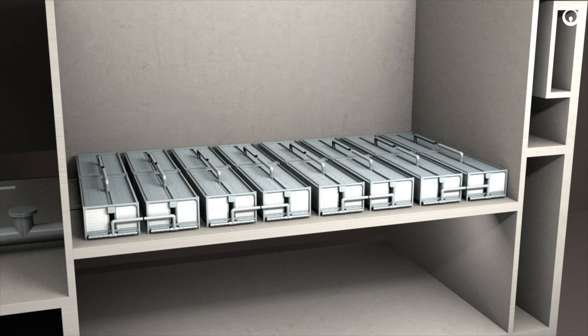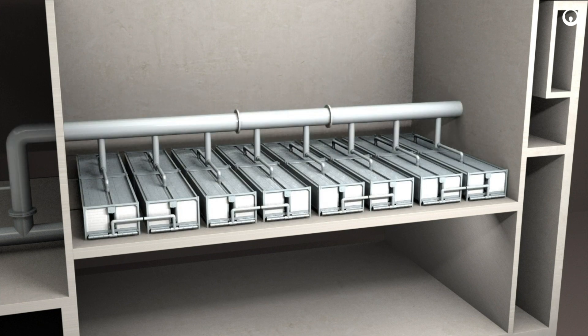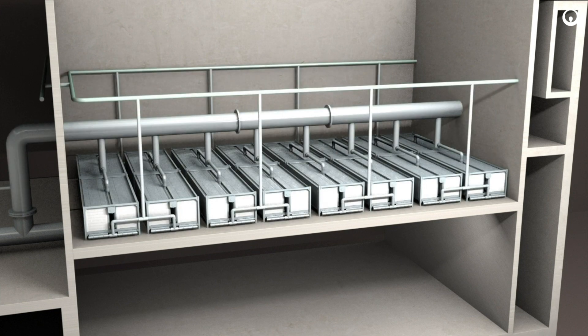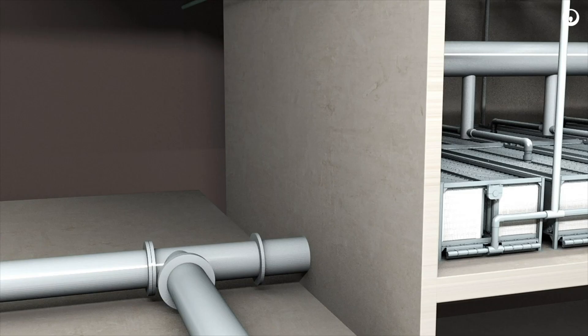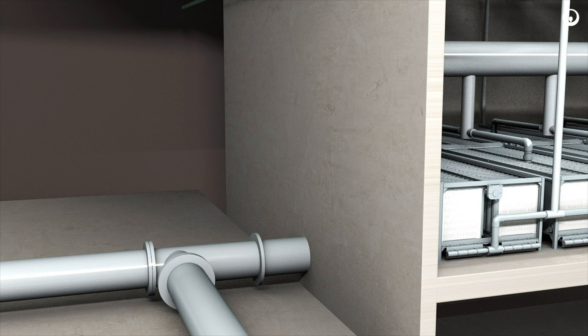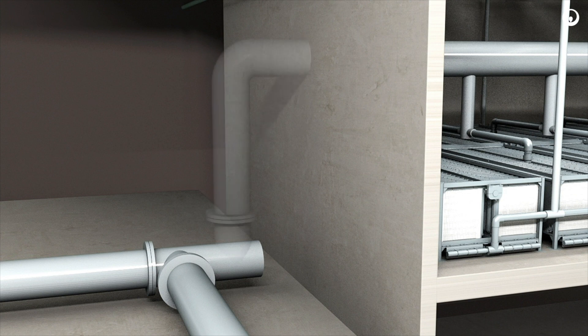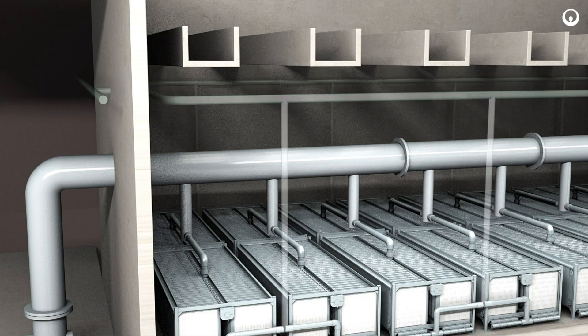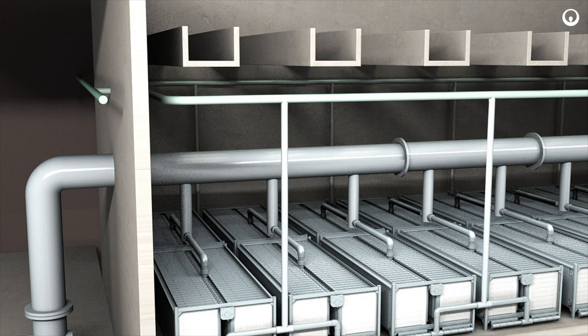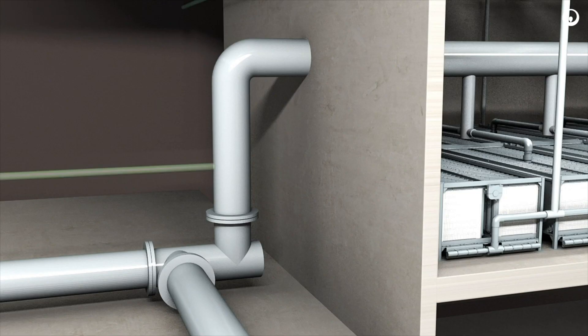Membranes are installed along with a new filtrate pipe, an air scour pipe to replace the underdrains. Outside of the filter, some minor changes are done to the piping. The filter underdrains are disconnected and replaced by a new filtrate and backwash pipe. The air scour piping is relocated.